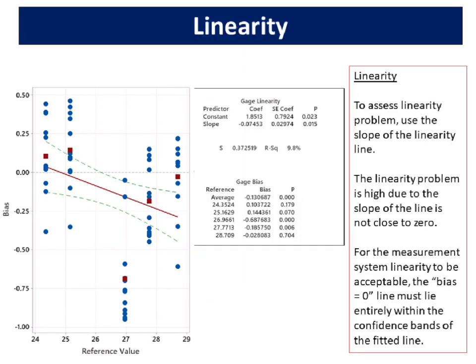Linearity: To assess linearity problems, use the slope of the linearity line. The linearity problem is high due to the slope of the line not close to zero. For the measurement system linearity to be acceptable, the bias equals zero line must lie entirely within the confidence bands of the fitted line.